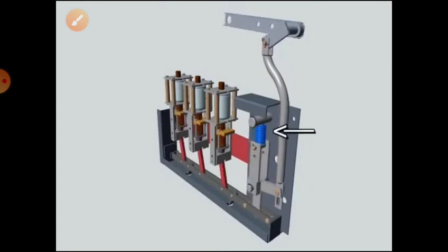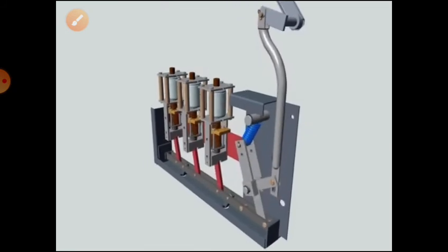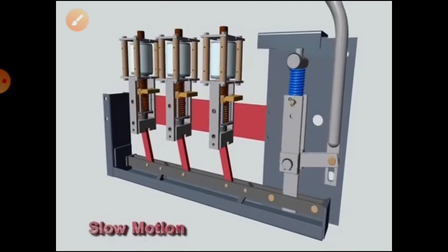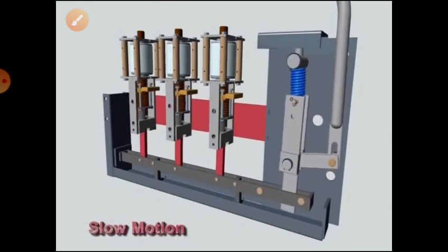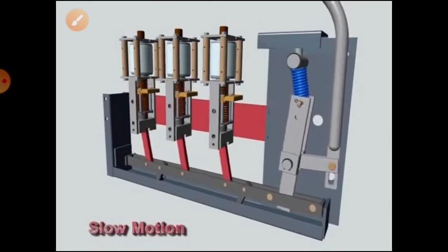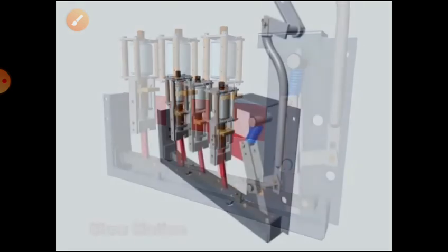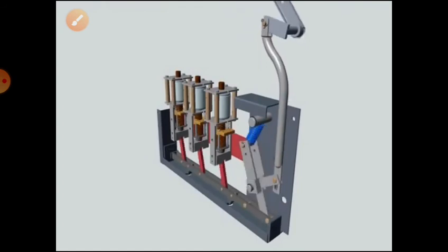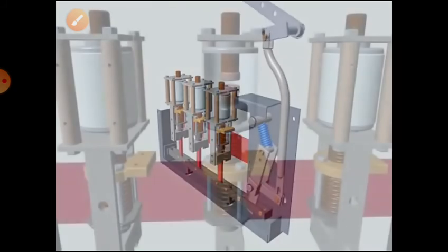A spring-driven toggle moves the switch position bar between two welded steel stops. On the closing stroke, the switch position bar moves up on its two pivoting support legs, driving the contacts to the closed position, and moves down during the opening stroke to pull the contacts open. The slotted operating linkage allows the mechanism's operating speed to be independent of the external switch operating handle.